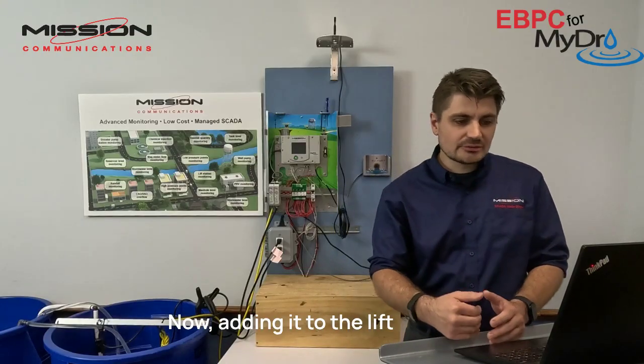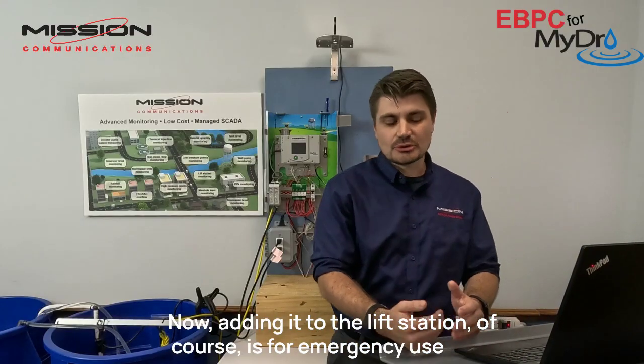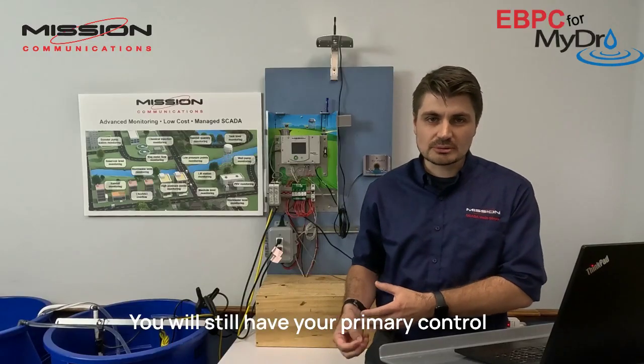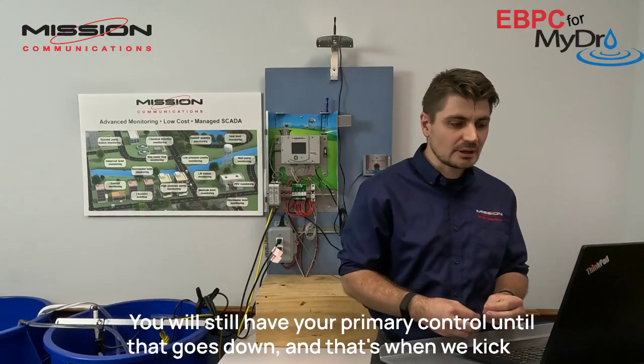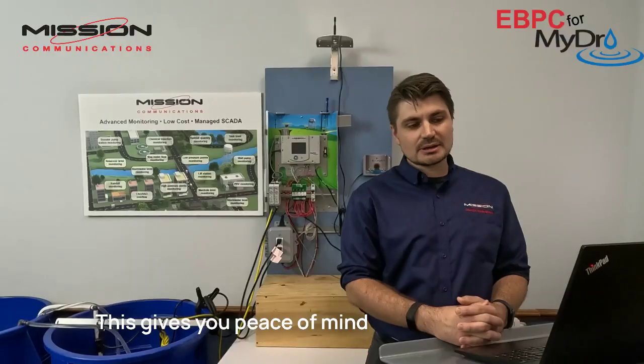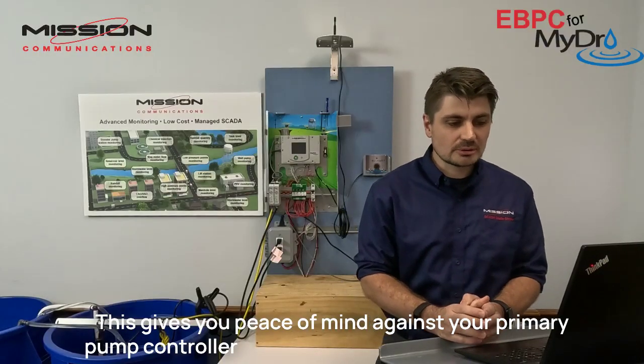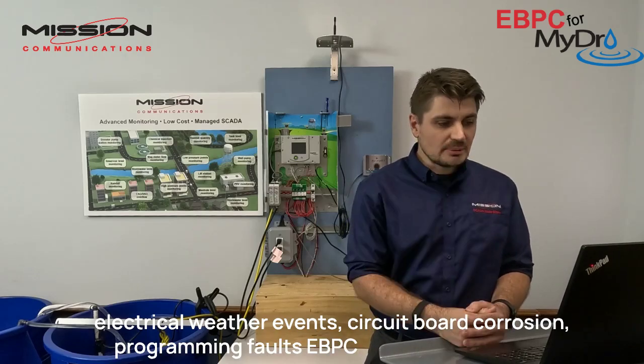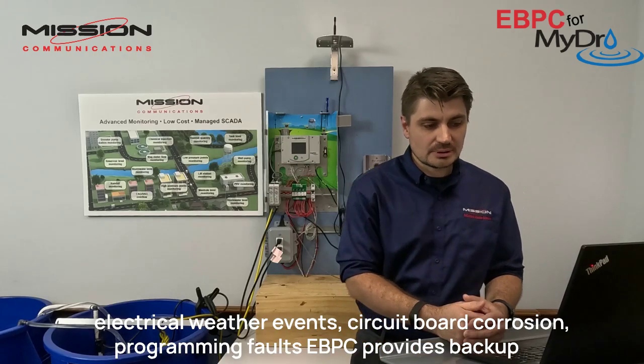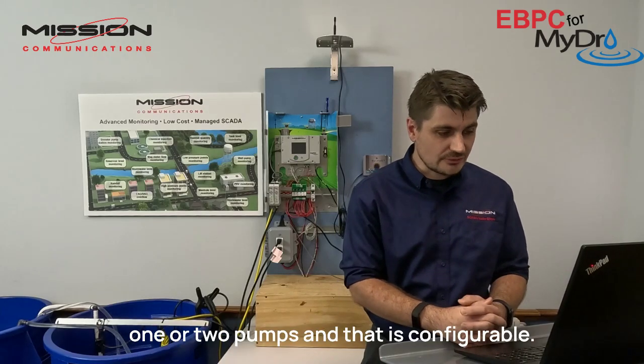Now, adding it to the lift station, of course, is for emergency use only. You will still have your primary control until that goes down, and that's where we kick in. This gives you peace of mind against your primary pump controller suffering any sort of damage due to electrical weather events, circuit board corrosion, programming faults. EBPC provides backup for 1 or 2 pumps, and that is configurable.